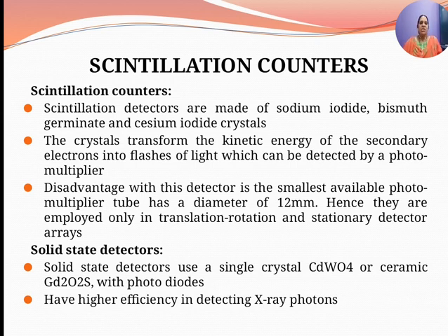Then your solid state detectors. The solid state detectors use a single crystal of cadmium tungsten oxide or ceramic Gd2O2S with photodiodes. They have high efficiency in detecting X-ray photons.